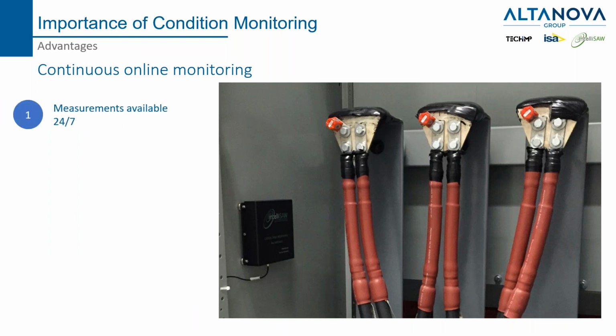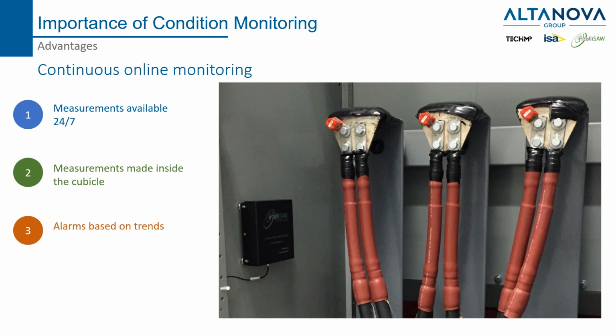Continuous online monitoring means that the measurement is available 24/7. The measurement is made inside the cubicle or outside, depending on the technology, can provide alarms based on trends and does not require a skilled operator. Basically, we are used to saying that the monitoring system is looking at the asset for the operator, it is the eye of the operator on the asset.